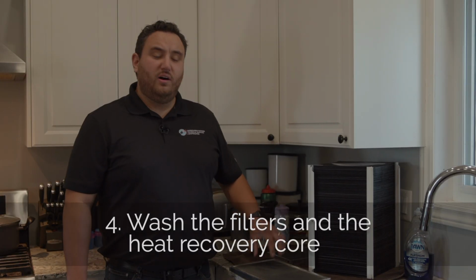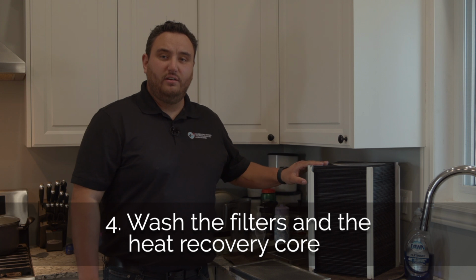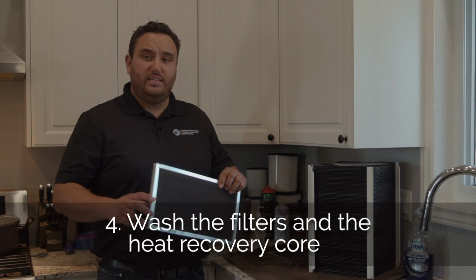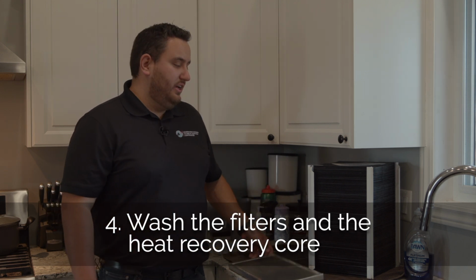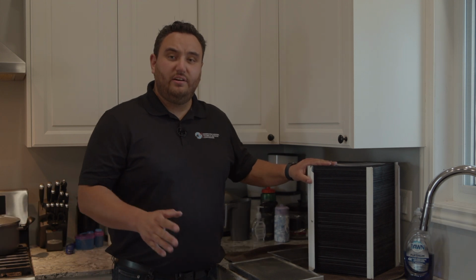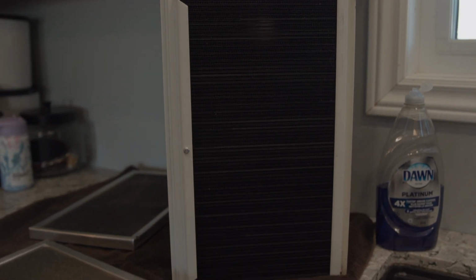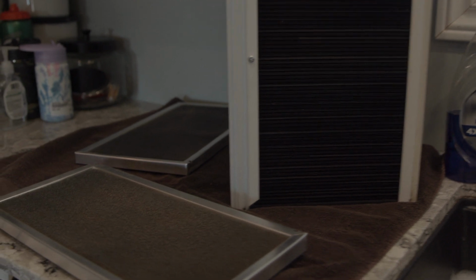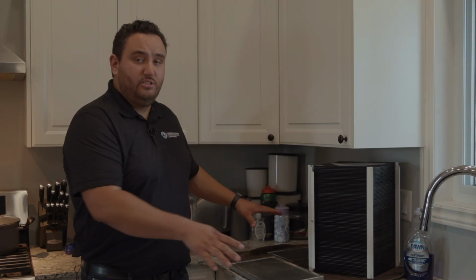Now we're going to go ahead and wash the filters and the heat recovery core. The filters can be washed every season or every 3 months. The heat recovery core should be washed every year at the end of summer. The heat recovery core can soak in the warm water for up to 3 hours, and you want to make sure everything's totally dry before putting it back in the unit.